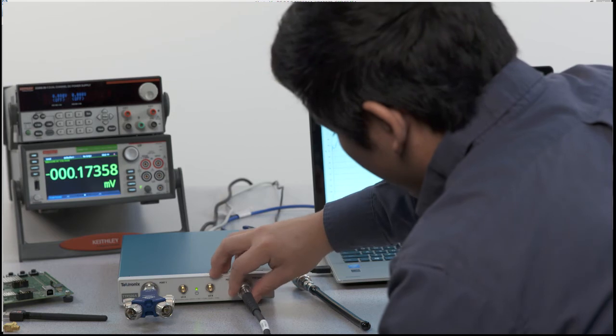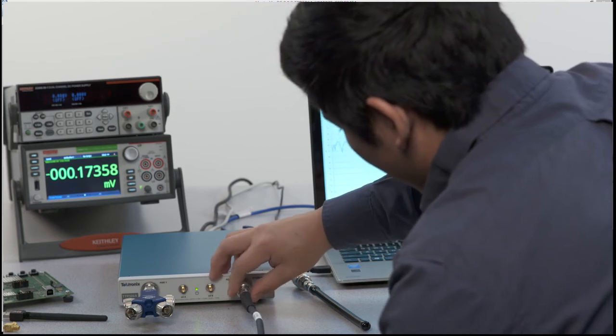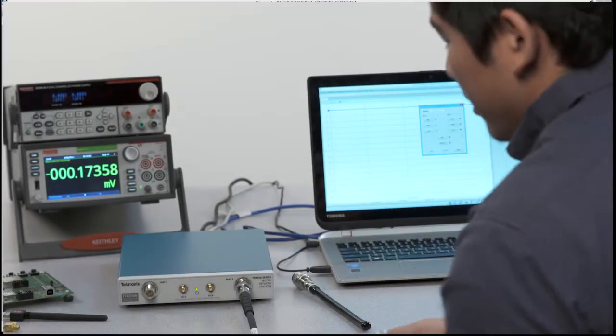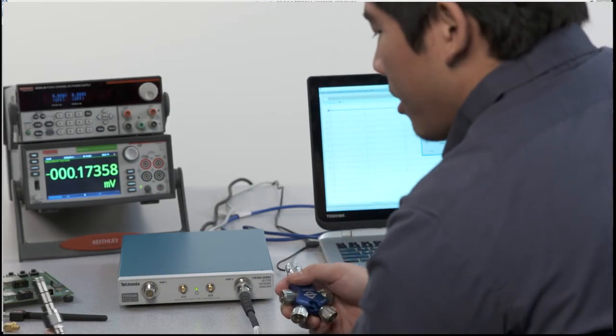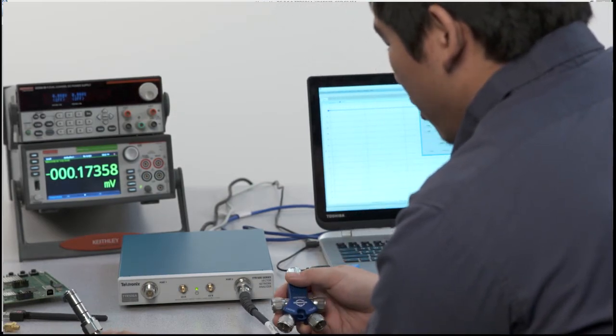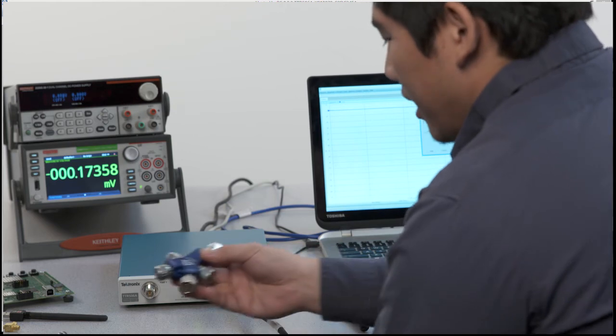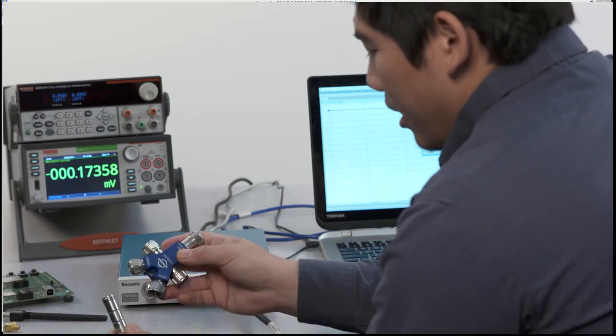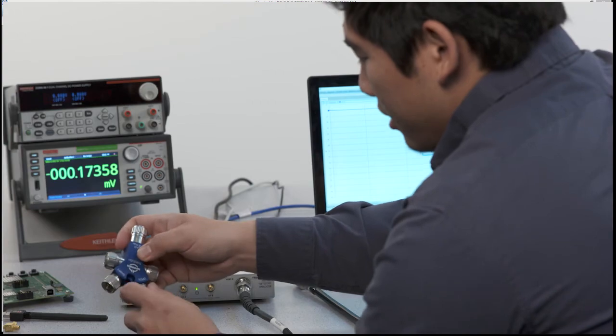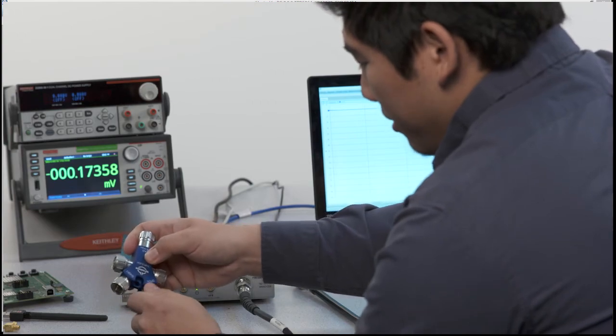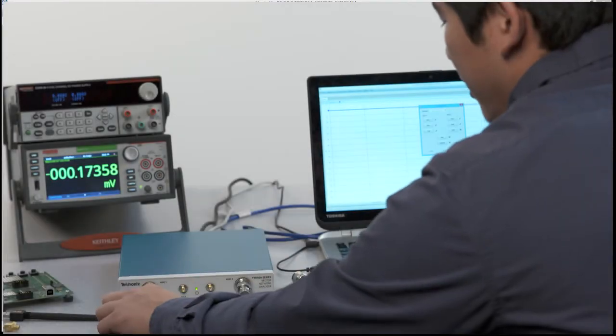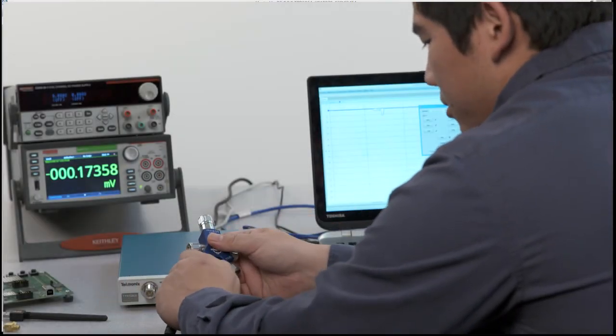So we're going to connect our type N cable to port 2 and we're going to repeat this procedure all the way through again: open, short, and load. But instead of doing it on the port we're going to do it at the end of this cable, starting with open for port 2 and finally load for port 2.